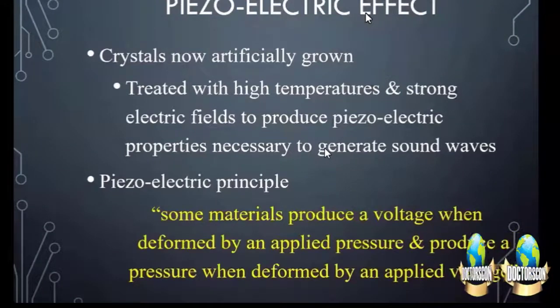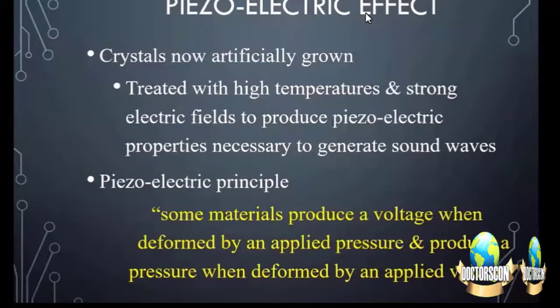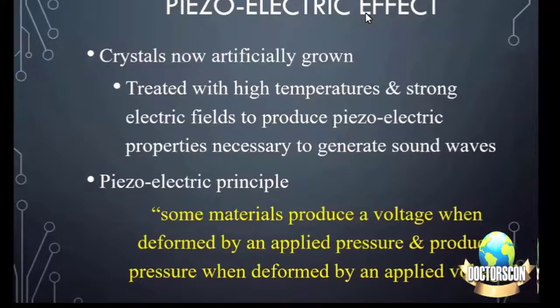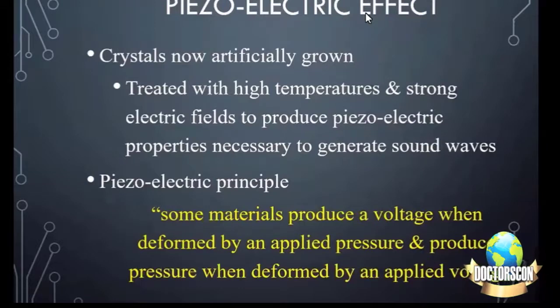So the basic theme is, due to voltage stimulus, the sound waves are produced from the crystals. The crystals are the structures which are piezoelectric, and they produce sound waves. Sound waves travel, strike different organs of the body, come back, and are recaptured by the transducer. When these pressure waves come back, they again strike these piezoelectric crystals, and those messages are taken by the receiver of the machine and shown as images in the form of white and black dots, which is on B mode. These crystals are nowadays artificially grown and treated with high temperature and strong electric field to produce piezoelectric properties necessary to generate sound waves.